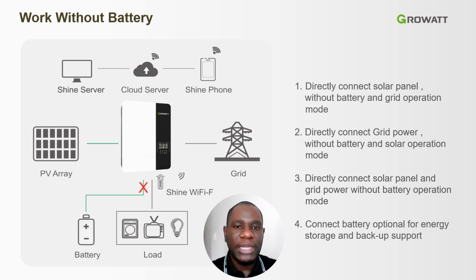Then this inverter, as I mentioned, can work with or without a battery. So this will save the initial installation cost to the client. As you can see, that diagram represents a system with or without a battery, with that red X showing you that this system can work without a battery. So you have 1 to 4 configurations or setups that you can operate this system in. For example, if you look at option 1, you can have a connection direct to the solar panels without the battery and grid operation mode. Or option 2, directly connect your grid power without the battery and solar operation mode. And so on with option 3 and option 4.